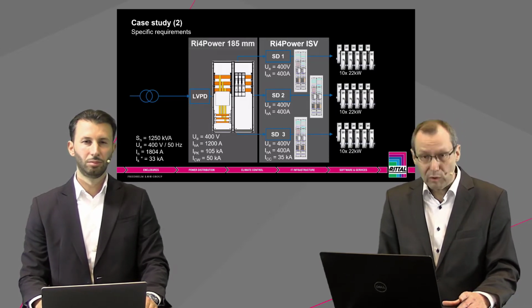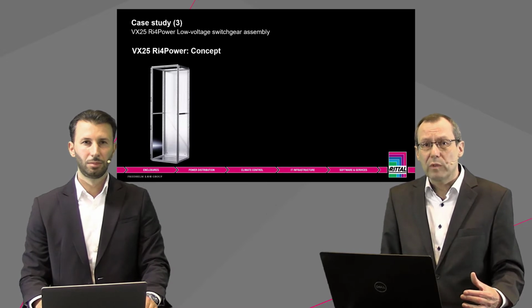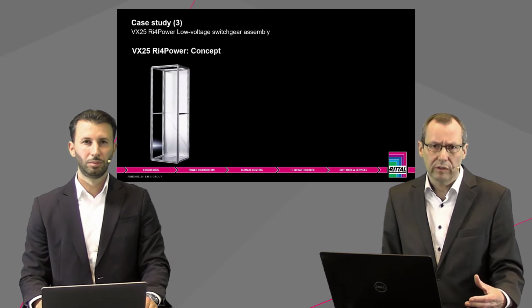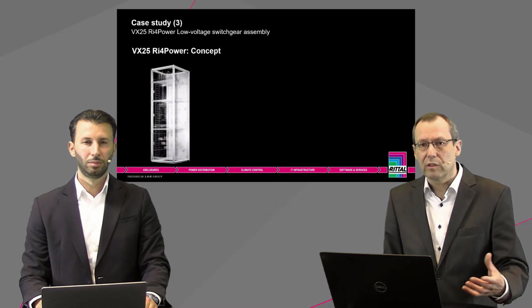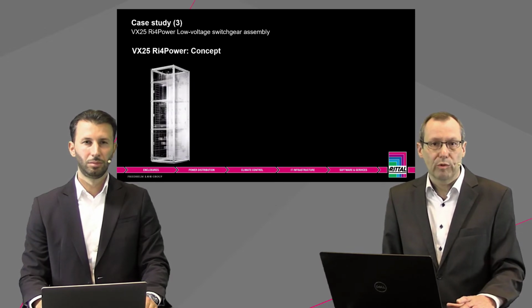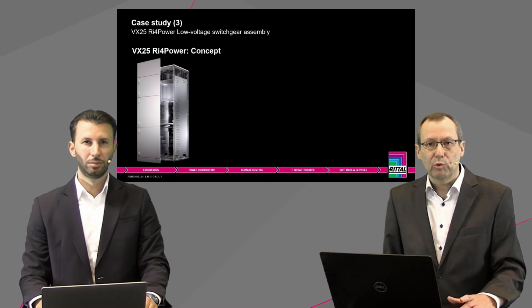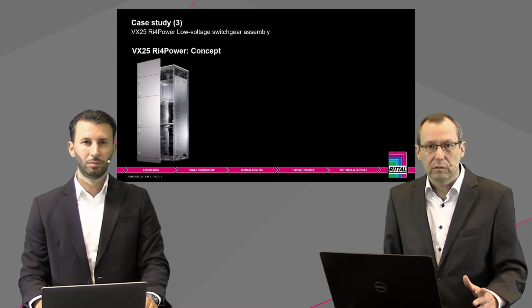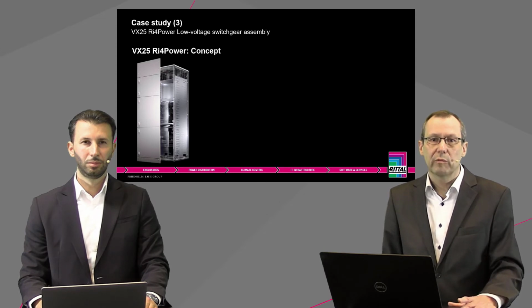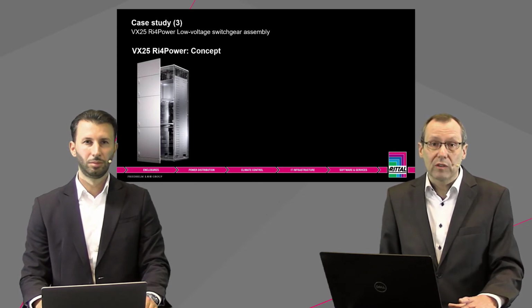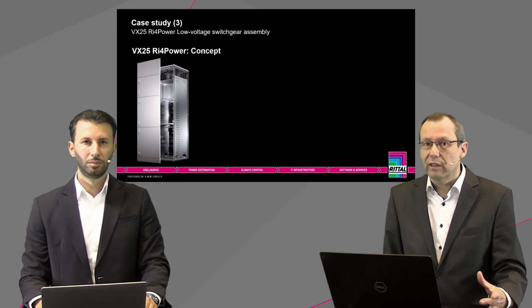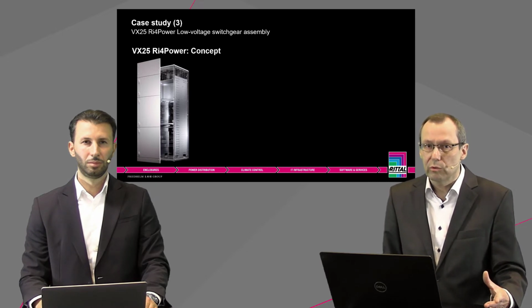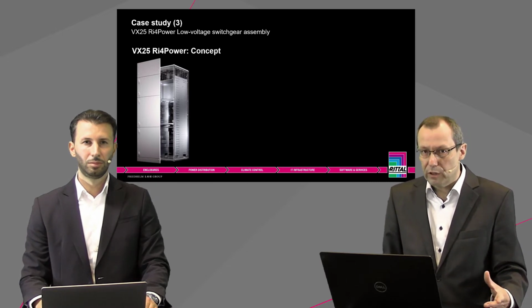The Ri4Power system is based on the VX25 as the enclosure, the basis for that system. In combination with different accessories for interior installation, such as dividers for internal separation, or modular fronts with partial doors and front trim panels, we're able to provide a modular system so anybody can create individual designs of internal form separation, according to IEC 61439 Part 2.